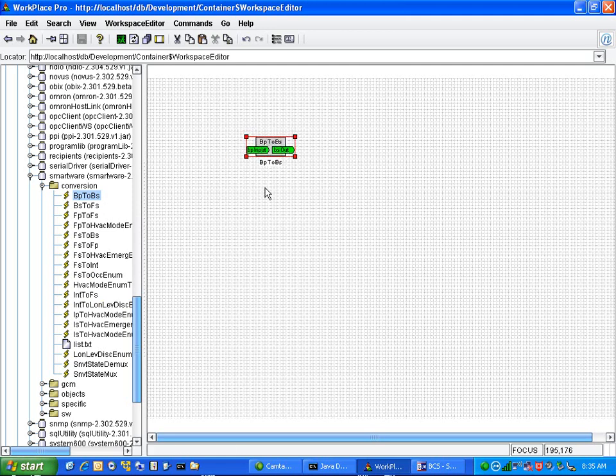And simply, when we had our other class where we talked about the out-of-the-box objects, I tried to explain that there were differences between status outputs and priority outputs. Priority outputs have a priority array, and they do not link to each other. So take a BP, for example, to a BS.